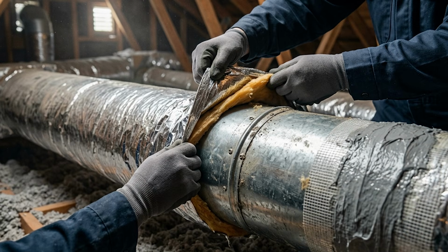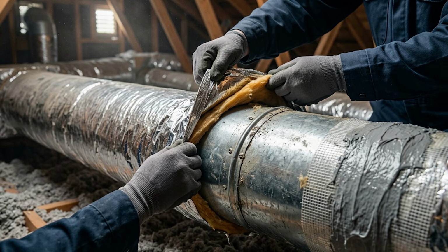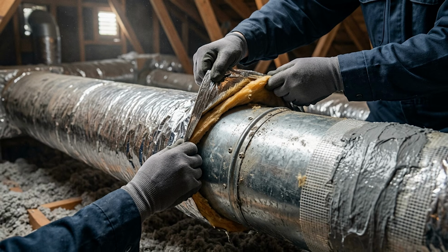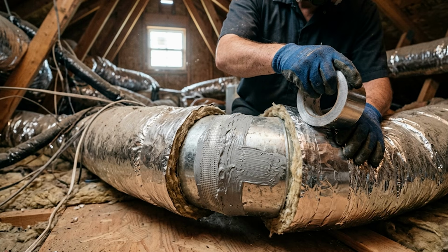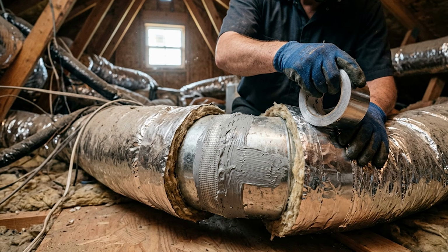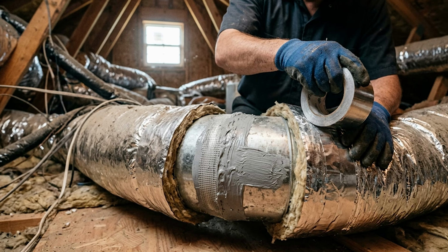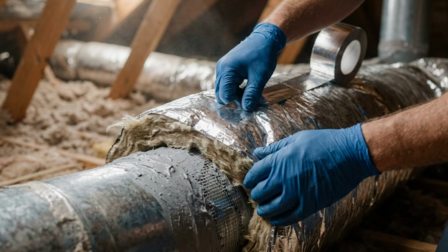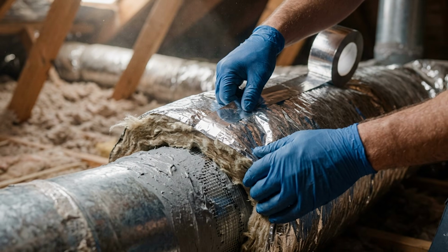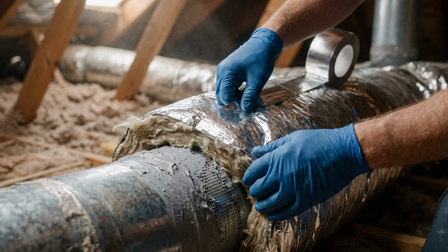For ducts that are wrapped in insulation, which most attic ducts are, peel back the insulation jacket carefully, seal the joint underneath, let it cure, then rewrap the insulation and seal the jacket closed with foil tape. Take your time with this step. Disturbing the insulation hastily can reduce its effectiveness.